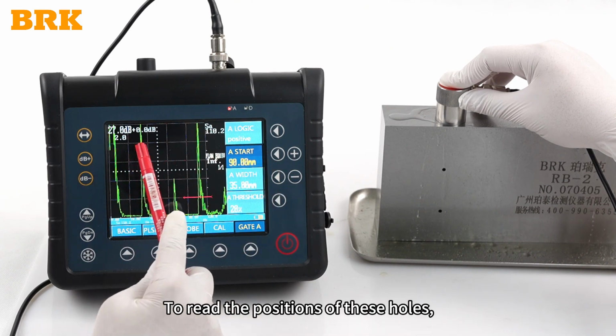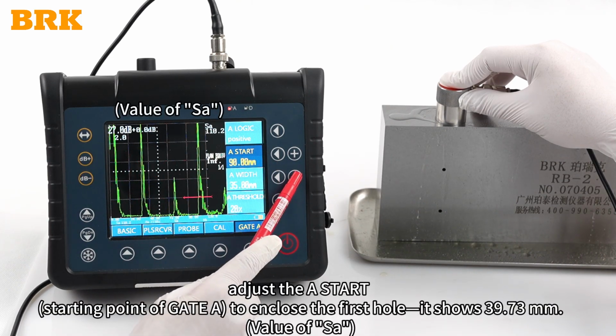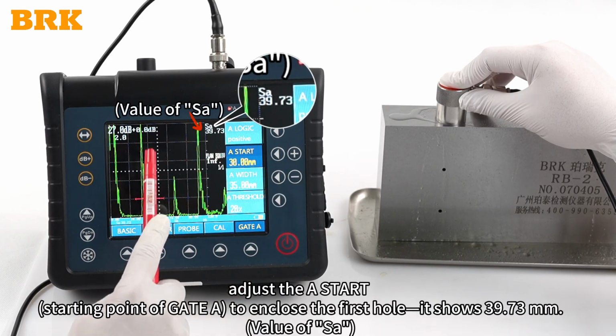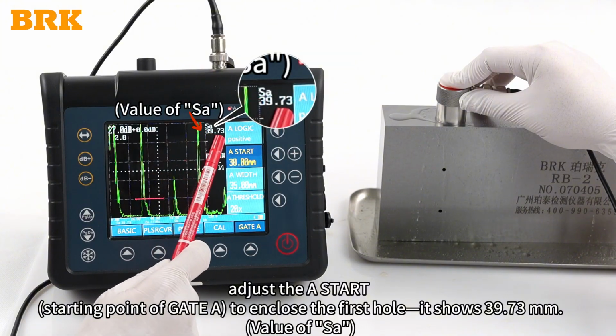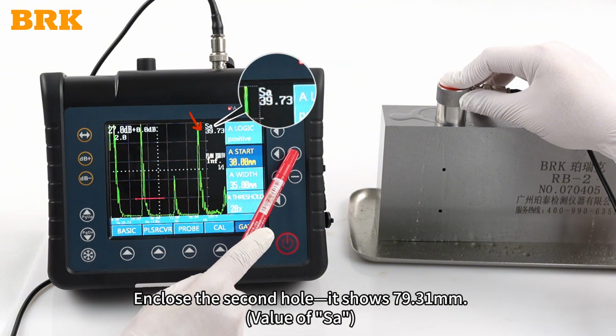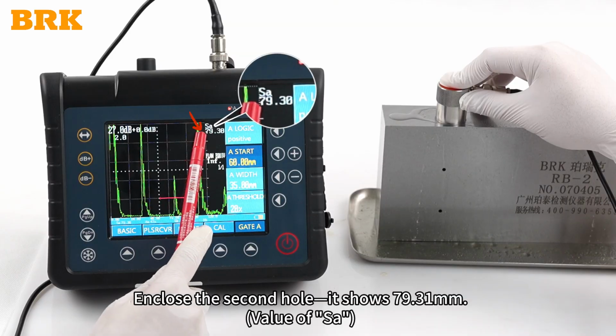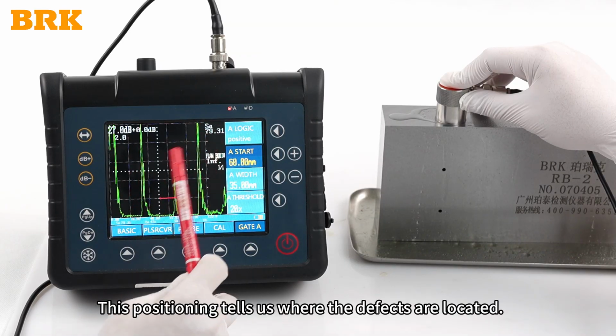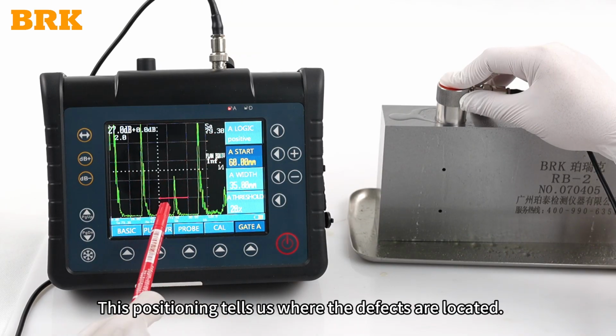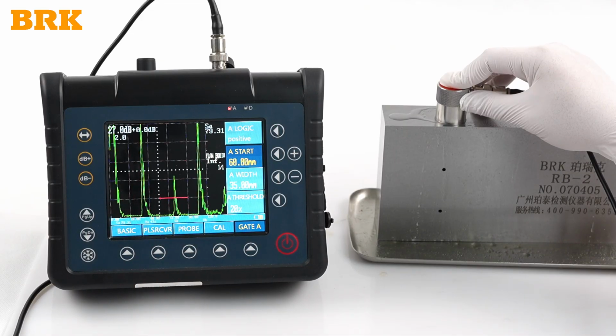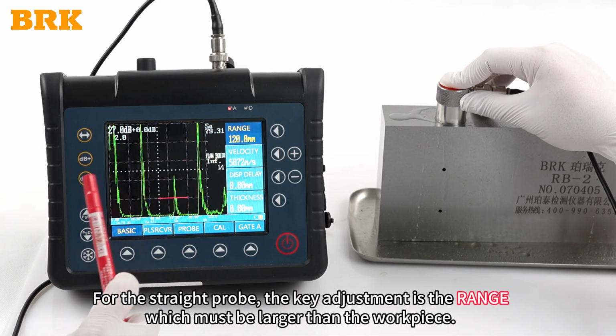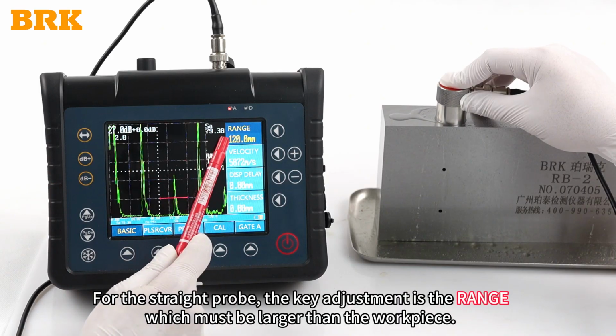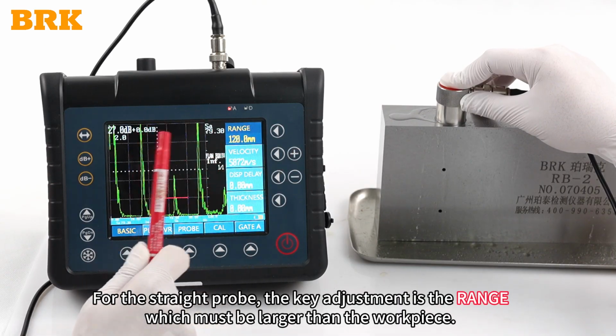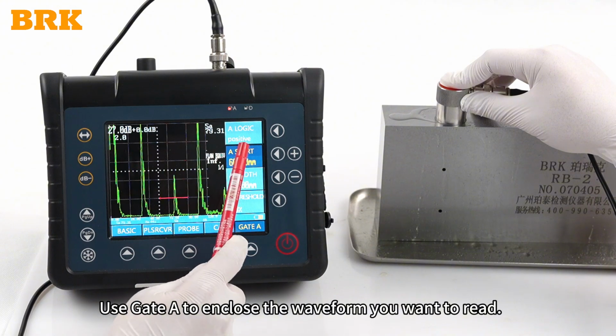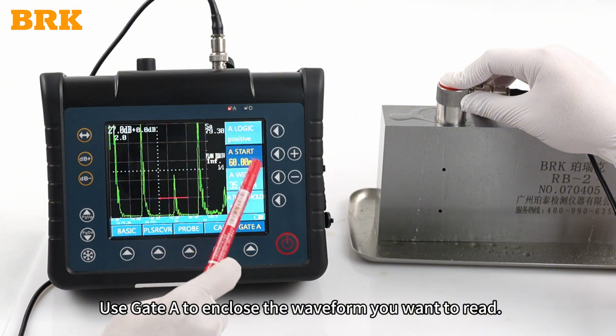To read the positions of these holes, adjust the starting point of gate A. To enclose the first hole, it shows 39.73 millimeters. Enclose the second hole, it shows 79.31 millimeters, the value of SA. This positioning tells us where the defects are located. For the straight probe, the key adjustment is the range, which must be larger than the workpiece. Use gate A to enclose the waveform you want to read.